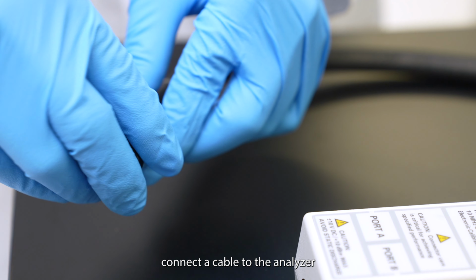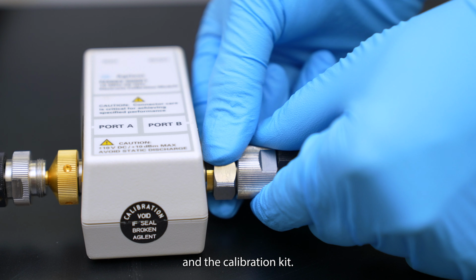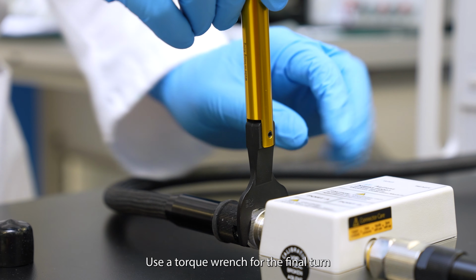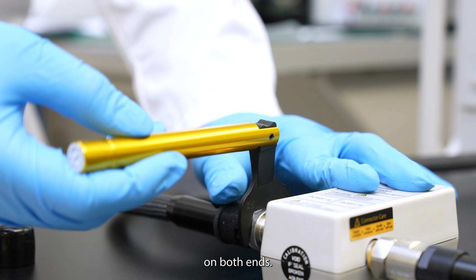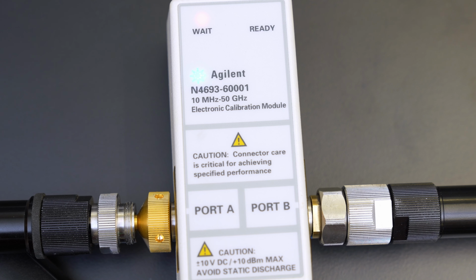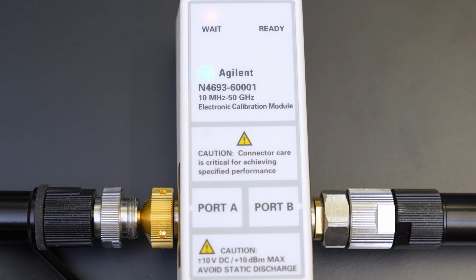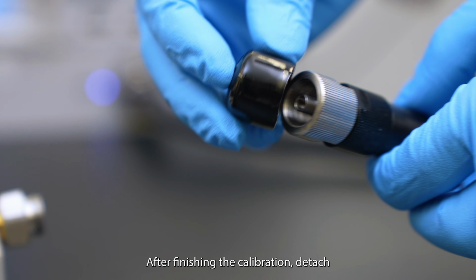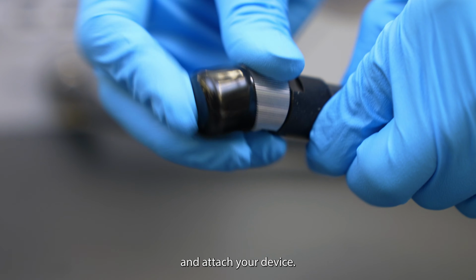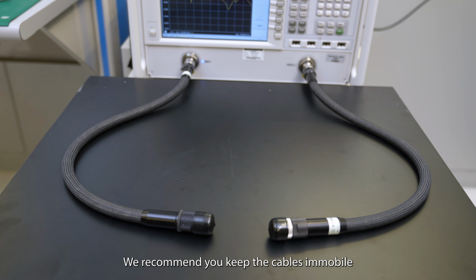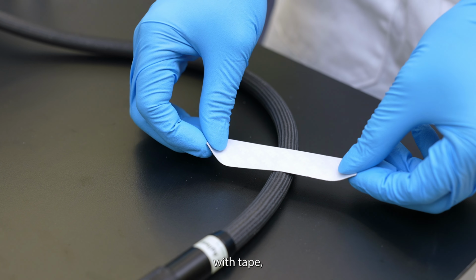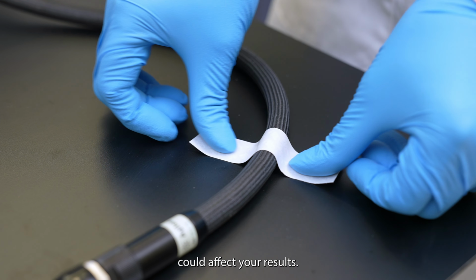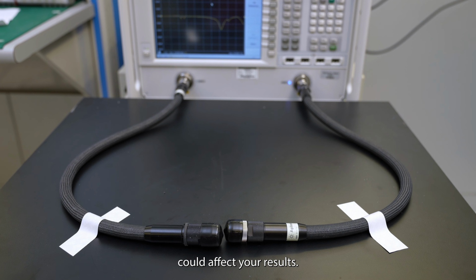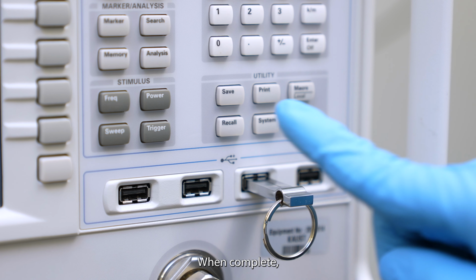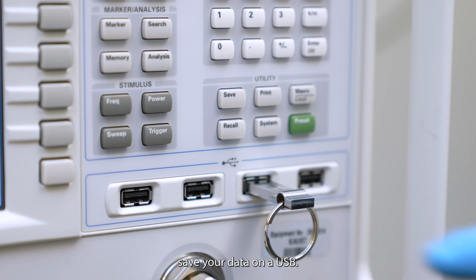Properly connect a cable to the analyzer and the calibration kit. Use a torque wrench for the final turn on both ends. After finishing the calibration, detach the calibration kit and attach your device. We recommend you keep the cables immobile with tape, as displacing them could affect your results. When complete, save your data on a USB.